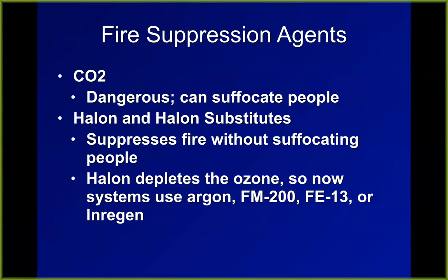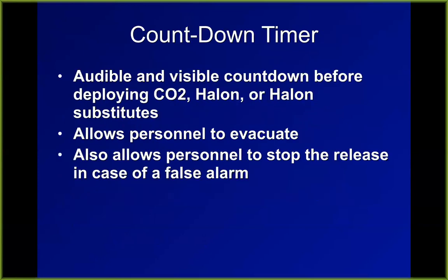CO2 is much better for the computers, but it can kill people if it pushes all the oxygen out of the room. Another technique people used in the past was halon. This stops the fire without suffocating people. But the problem with halon is that after you've used it, it escapes into the air and goes up and depletes the ozone. So it's illegal to use for new deployments. And there are substitute systems, substitute chemicals using argon or FM200 or these other chemicals.